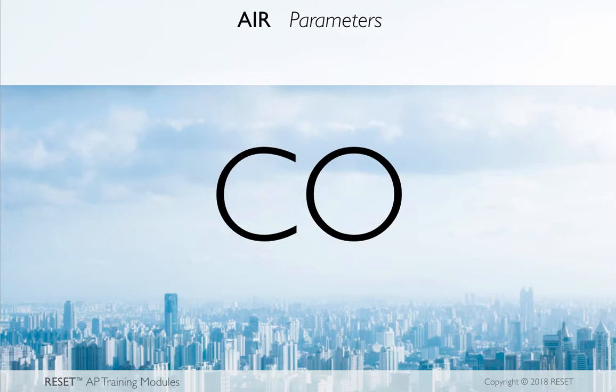So the last parameter that I want to talk about is CO. Now, just make sure that you understand, as you're talking about Reset, CO only needs to be monitored and reported if there is an area of combustion or in areas adjacent to where combustion might be present, such as above or below parking garages, heavy industrial areas and facilities, commercial kitchens, that type of thing.